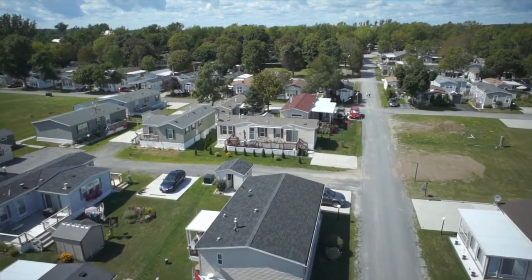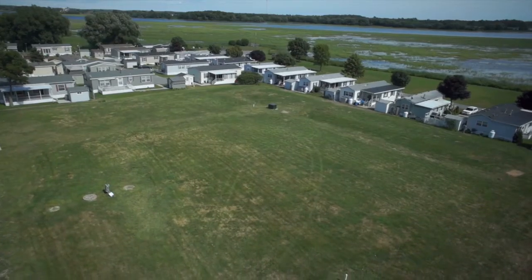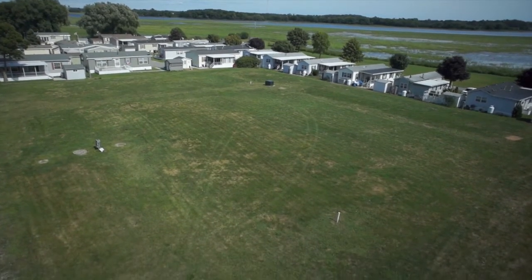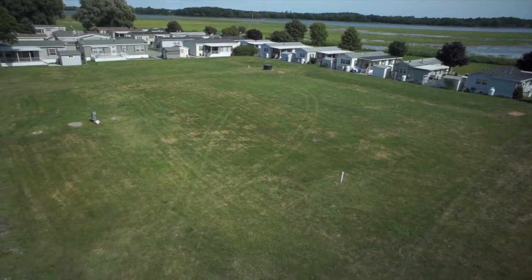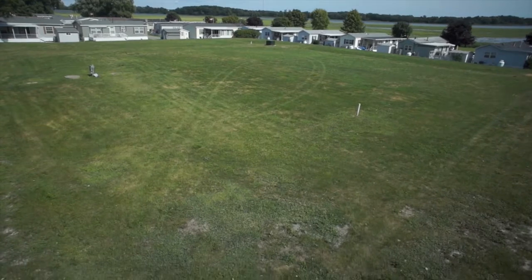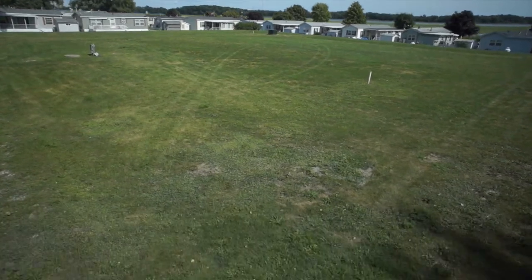They looked at options around rebuilding the subsurface bed and found that they potentially needed a different solution. The old bed was breaking down — we had to pump every day. We have three tanks in here that we had to pump out because they go in chambers, all pumping from the hill down to this bed. We'd have to pump them out two to three times a day, and with heavy rains and heavy infiltration through the old piping, sometimes four times a day — seven days a week for two years, until we got finalization to proceed with the new plan.